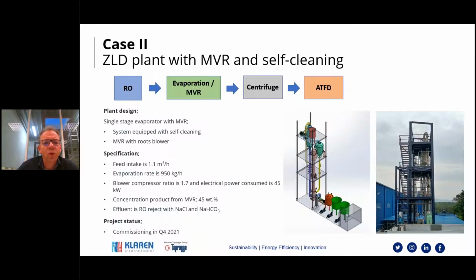MVR needs a compressor, and in this case, since the feed flow and evaporation rate is on the low side, I mean, low side is always relative, but low side if you talk about centrifugal compressors, we have chosen to use a roots blower. For the roots blower, we have chosen a compressor ratio of 1.7, balancing heat transfer area with power cost, but more detail to follow. But in overview, the blower in this case will consume around 45 kilowatts.